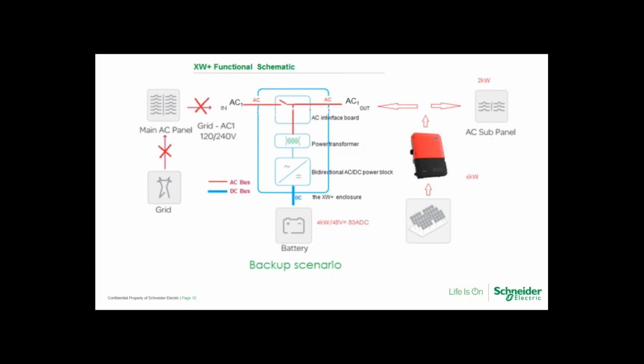So what's going to happen is whenever the load demand is minimal, then virtually all of that PV is going to flow through the output of the inverter into the battery, and that's going to go into the battery unregulated. And that's an important point because you want to make sure that, again, your battery bank is sized to accommodate the total current that could flow into it. So for example, if you have a 4 kilowatt array and you divide that by the nominal battery voltage of 48, that would give you 83 amps of DC current that could potentially be pushed into the battery. So it needs to be sized to accept that total current, at least that total current.